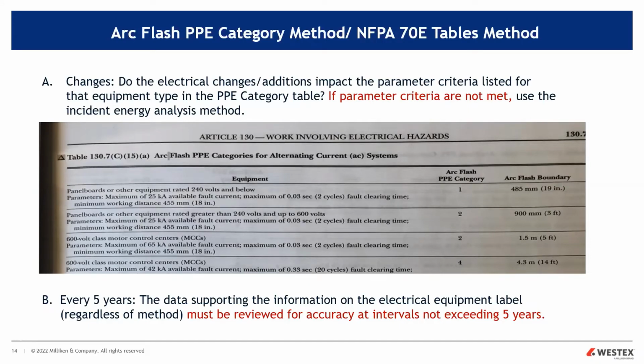So you see here, the top one there, panel boards and other equipment rated 240 volts and below. It has a maximum 25 kA available fault current. Clearing time is 2 cycles. It has a work distance. So if the maximum available fault current has been exceeded with your additions to your equipment, or the clearing time has changed or gone beyond the maximums because you changed the setting on the circuit breakers or added equipment, then you really can't use the tables if they don't meet these parameters, and you're going to have to use the incident energy method.